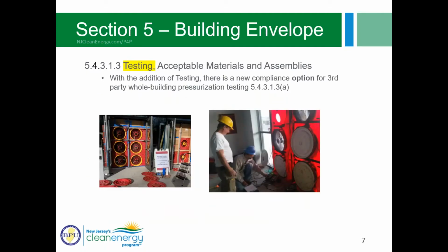All right, so we'll start with building envelope. So this section is one of the mandatory ones, where previously ASHRAE 90.1 had a list of acceptable materials and assemblies, and had provisions around leakage rates with those. Now, the 2016 version adds in the option for testing. So now we have this different compliance option where they'll actually do a whole building pressurization testing to see if it meets that requirement. So you can do testing or the acceptable materials or the assemblies that are listed there in 90.1.